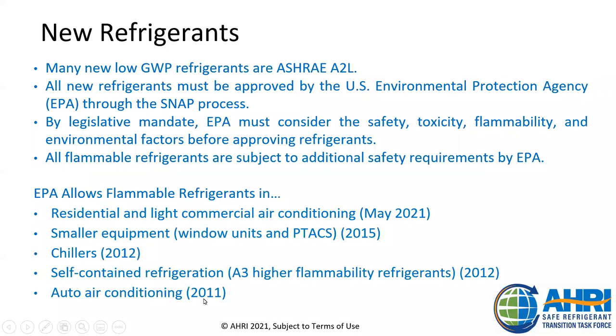And what does it mean, these new refrigerants? Many of the new low GWP refrigerants are ASHRAE A2L. What does that mean? All new refrigerants must be approved by the US EPA through the SNAP process. By legislative mandate, EPA must consider safety, toxicity, flammability, and environmental factors before approving new refrigerants. So many of the new low GWP refrigerants that are ASHRAE A2L will also have to be approved by the US EPA. And those will be subject to additional safety requirements by the EPA.